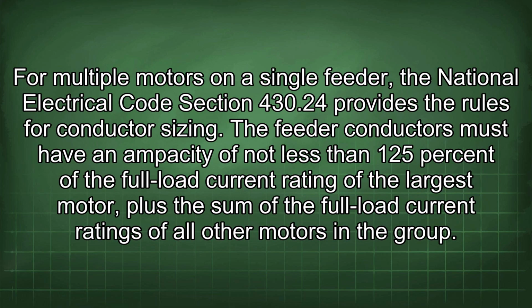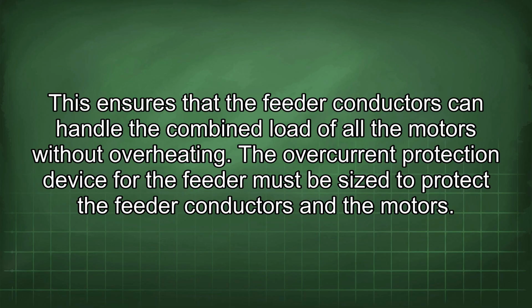For multiple motors on a single feeder, the National Electrical Code Section 430.24 provides the rules for conductor sizing. The feeder conductors must have an ampacity of not less than 125% of the full load current rating of the largest motor, plus the sum of the full load current ratings of all other motors in the group. This ensures that the feeder conductors can handle the combined load of all the motors without overheating.